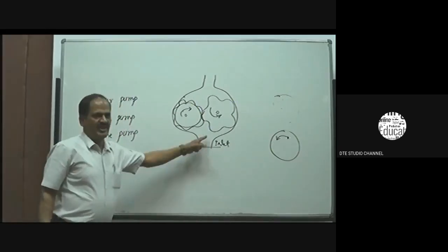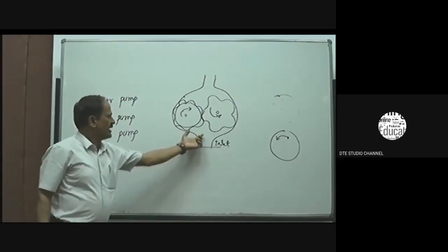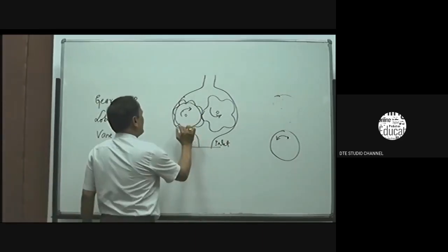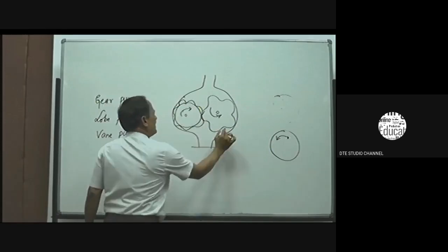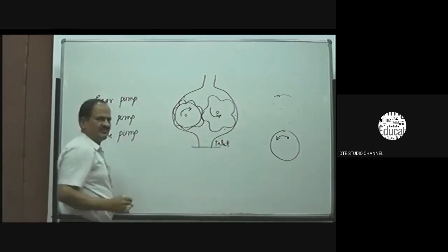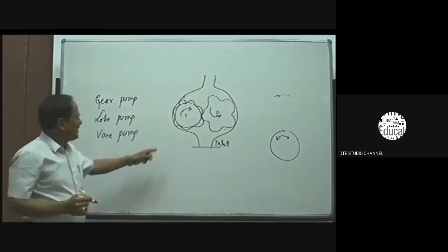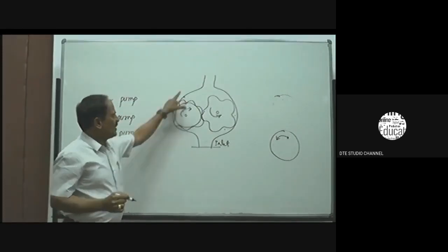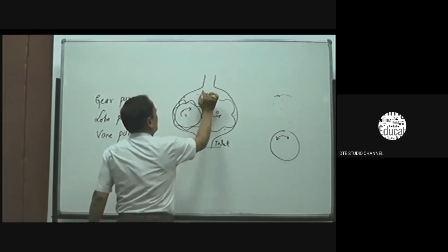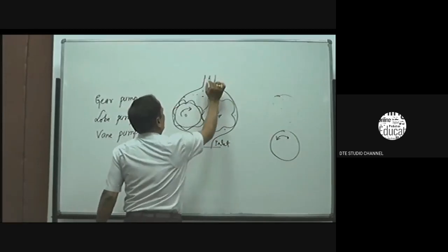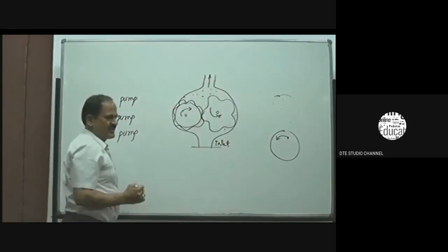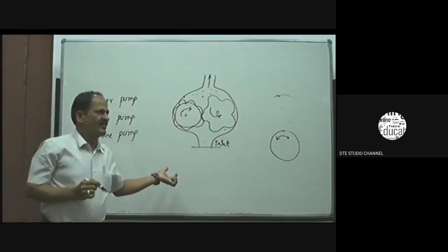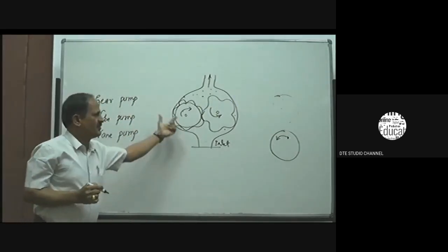Due to pressure difference, it draws fluid into the inlet, and the fluid is trapped between the teeth of driving and driven gears as they rotate. And the pressure of a fluid is gradually increasing from inlet to the outlet, and at the outlet, fluid is discharged at high pressure. This is a basic principle of working of any gear pump.